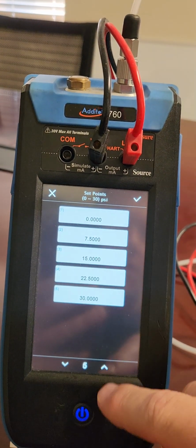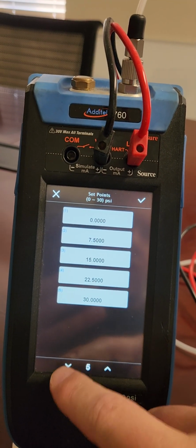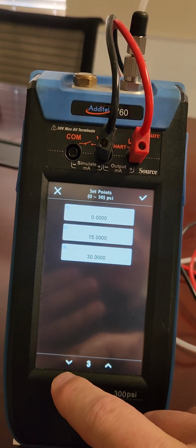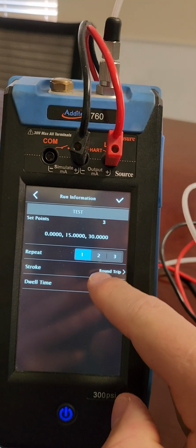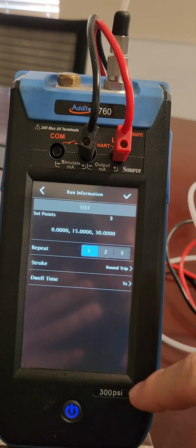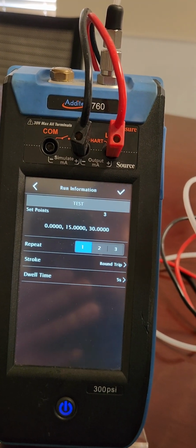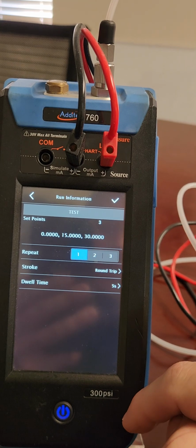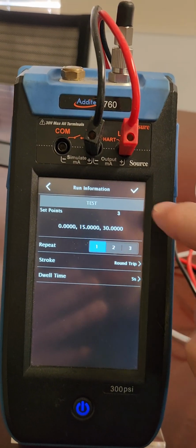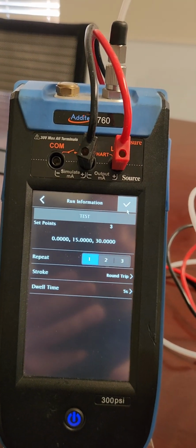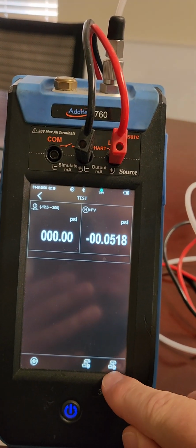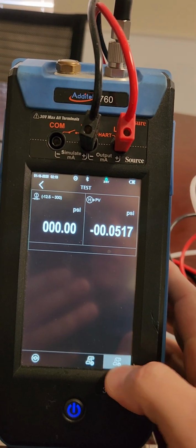Select my point. You can change this to whatever you want it to be. I'm just going to do 3 points for this. Repeat, so if you want to repeat the calibration. Round trip, so it goes up and down. This is nice because it looks at hysteresis and then your dwell time. So you have that all set up. You hit check mark, make sure everything's reading correctly. You hit auto. And then it's going to run through the calibration.